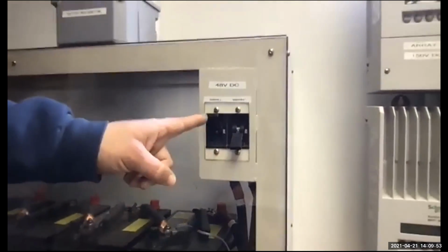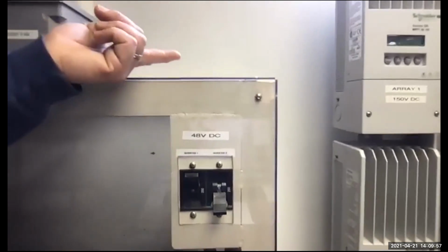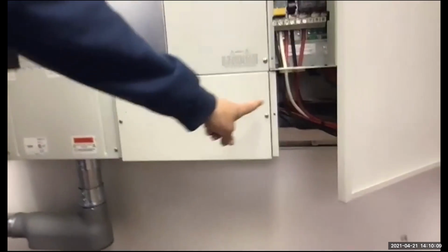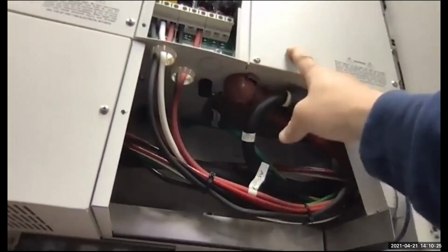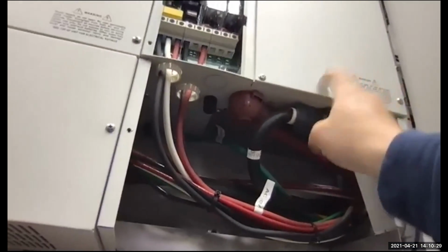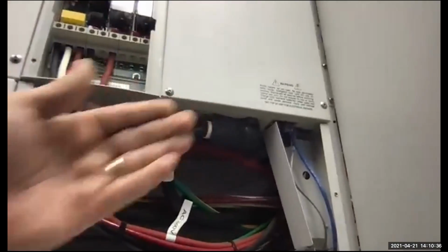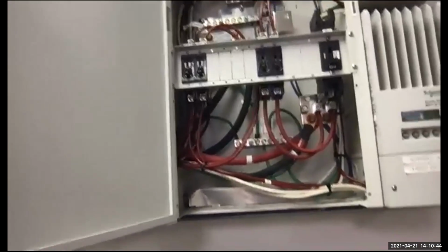Then we have our positive cable that comes up, goes through the breaker, back out the breaker, back into this channel down here, and through this pipe right here. Then it comes all the way over through this trough, and we can see the wires right there. So what we notice is there are these little caps up here protecting our wire. So we have more or less a positive connection to our inverter for our battery, and a negative connection for our inverter on our battery. So the positive and negative connections now run from our inverter over to our bus bar, because the actual battery cables that run all the way through here, through our little trough, they go to the bars first.